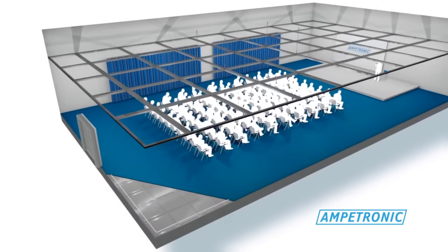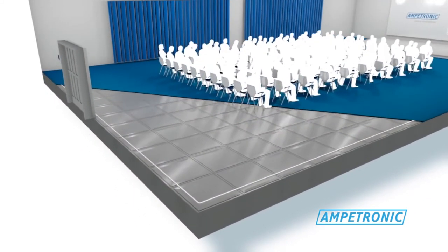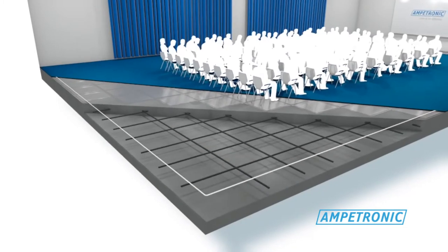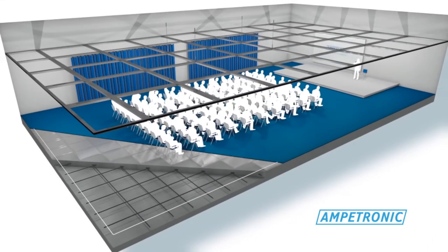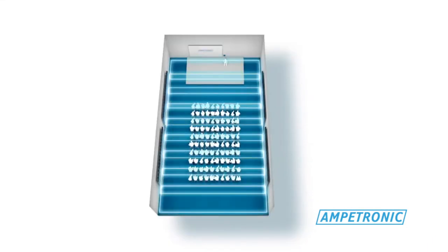You can't always use a perimeter loop around a room, as many modern buildings contain metal that absorbs the hearing loop's magnetic field.